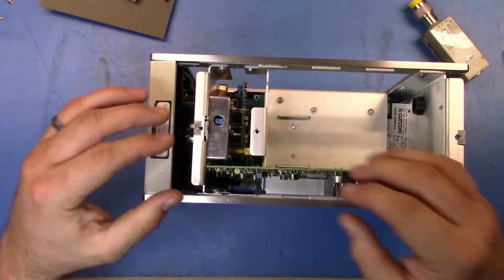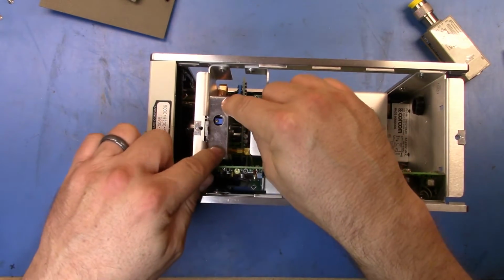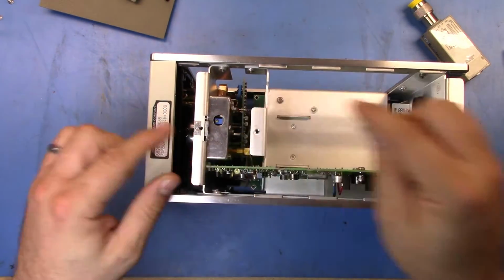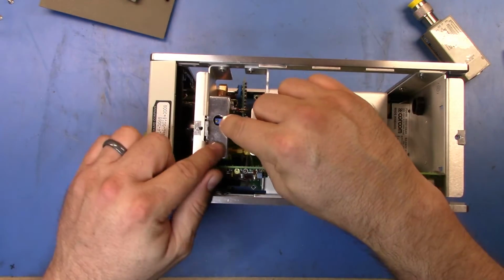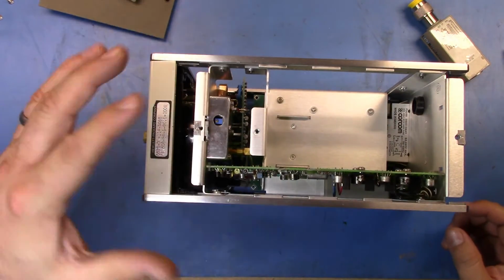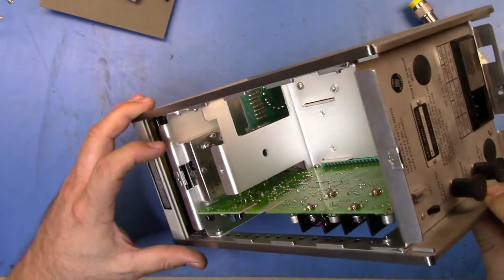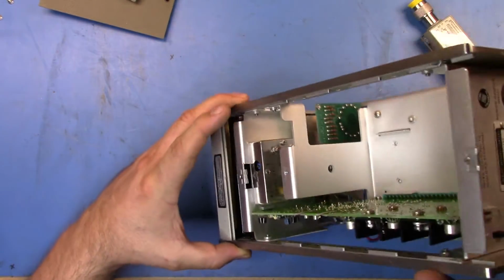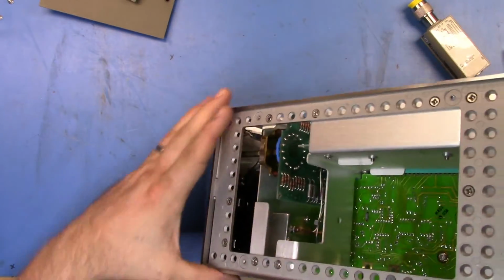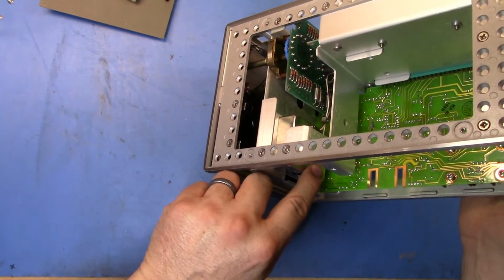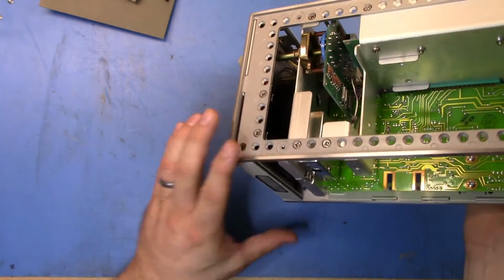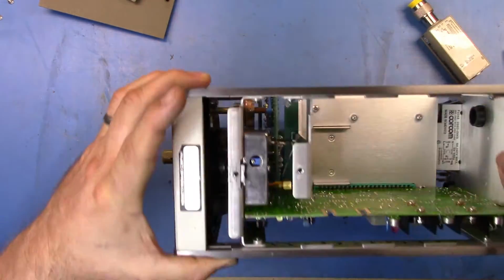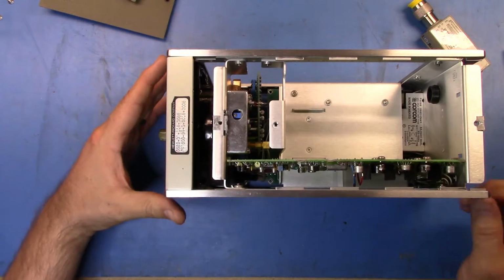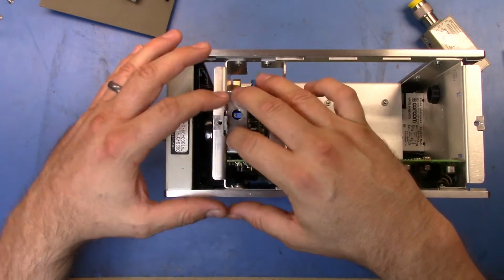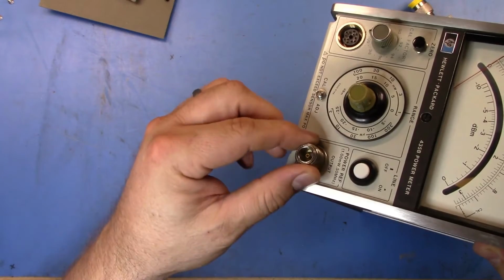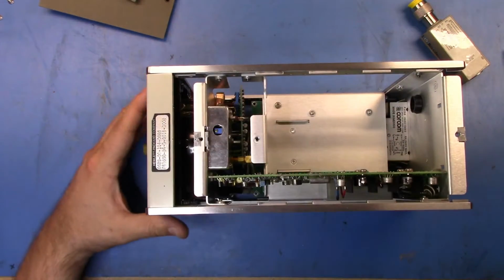If we look in a bit closer, this is the 50 megahertz reference, the 0 dBm 50 megahertz reference. And you can see this control here is what you use to set the level. And then on the control, I'm going to see if we can get a better view of that. There, inside this can here are some settings that will control the oscillation and the frequency that it will oscillate on. But that basically exists solely to run this power reference here and to give you that known standard.